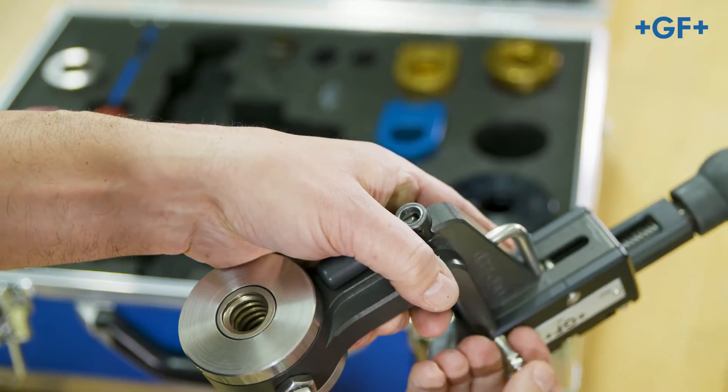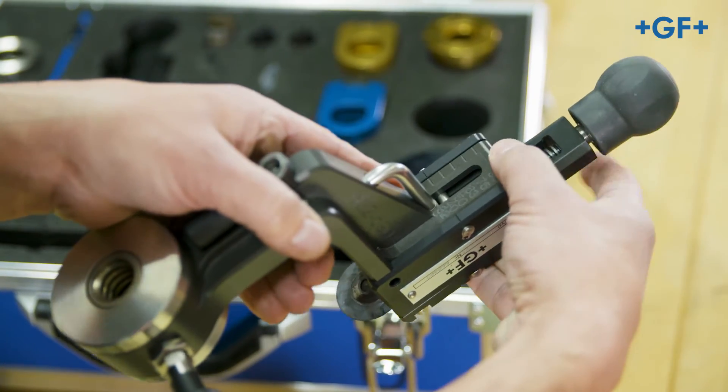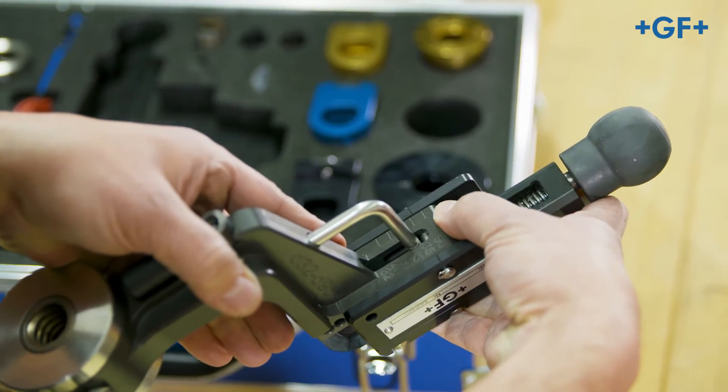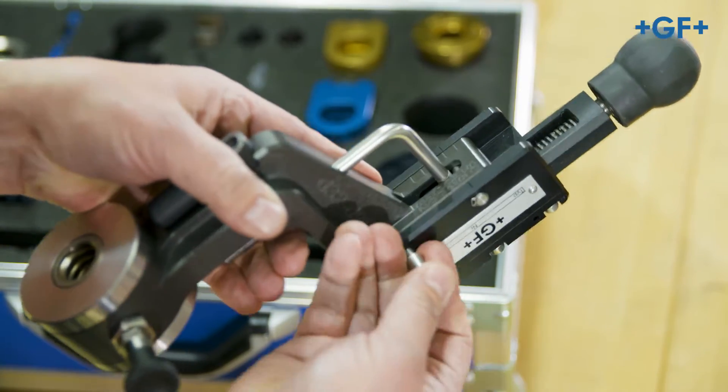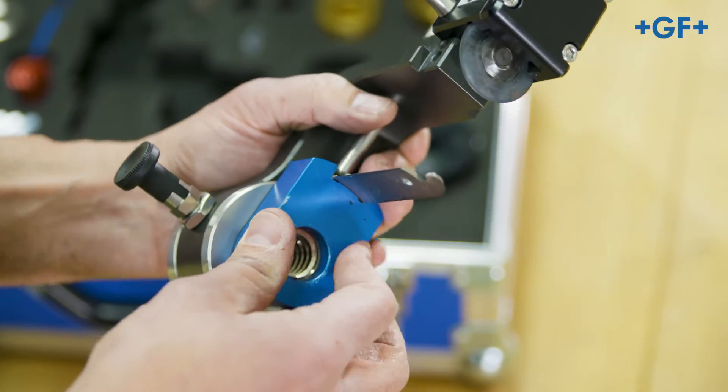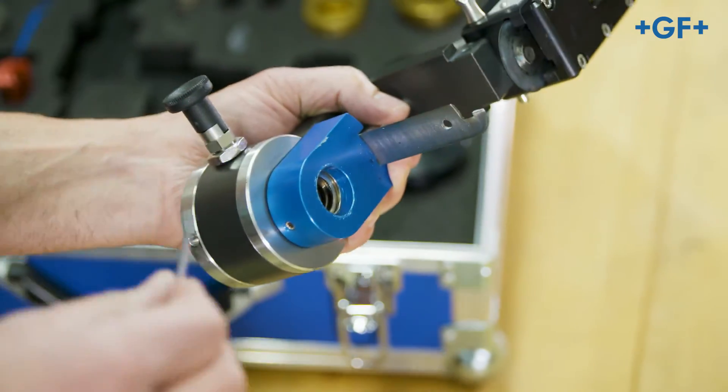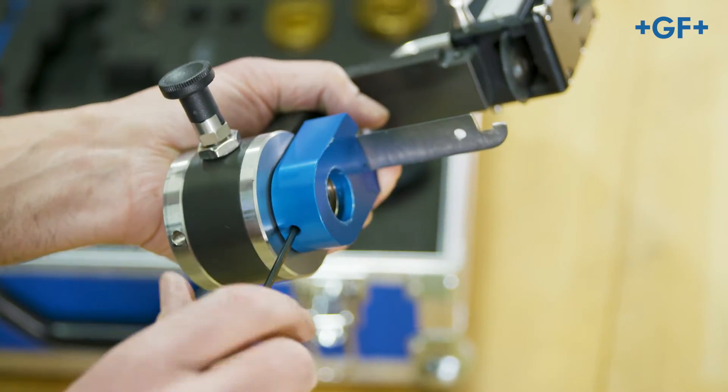Set the circular blade device of the foam removal unit according to the chosen CoolFit pipe diameter. Mount the corresponding peeling blade according to the CoolFit pipe diameter onto the foam removal unit and tighten it with the Allen key.